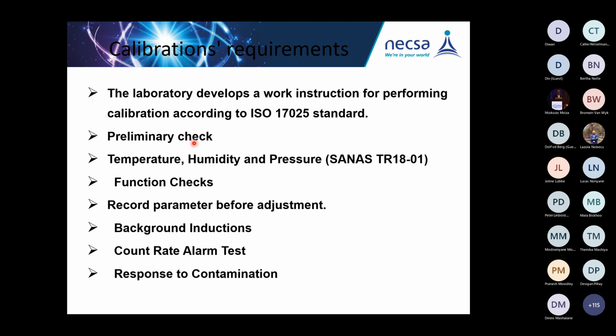If the laboratory is accredited, we perform the preliminary check. The preliminary check is to check if the instrument is still working fine, if everything is okay, and calibration is performed under a controlled environment. The set requirement for temperature is 20 plus or minus 5 according to SANAS TR 18. We also check the functionality, that is, whether the instrument is still doing everything according to what the manufacturer intended or designed it for. And we record the parameters before we commence with the calibrations.